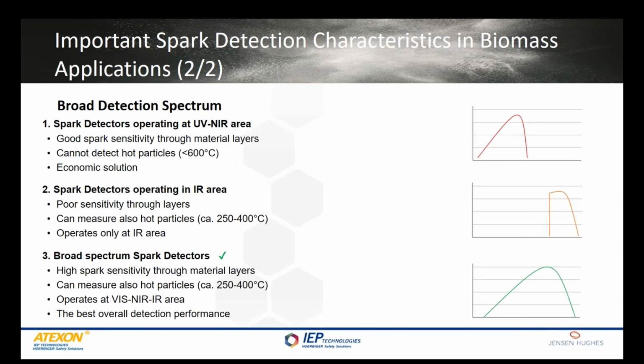Another important need the biomass industry sets for spark detectors is the detection spectrum. Hot particles are very important to detect because biomass applications have a lot of reasons for producing them, and they can easily ignite a fire or dust explosion. However, hot particles having a temperature less than 550 Celsius degrees do not emit any daylight. For that reason, infrared detection is needed. A drawback of infrared radiation is that water absorbs it and biomass always contains some moisture. We also know that if we are using a portable or handheld infrared temperature meter, we are always measuring the surface, but not what is behind the wall or surface.